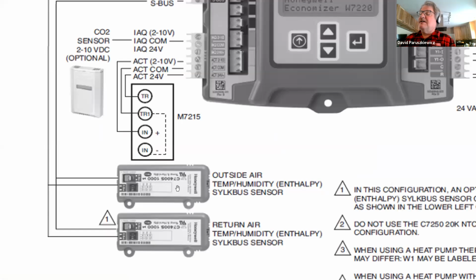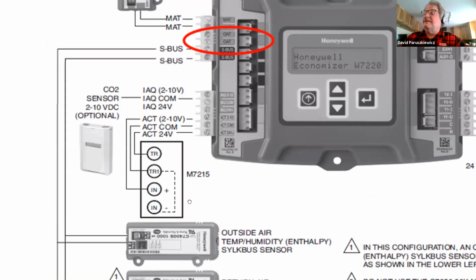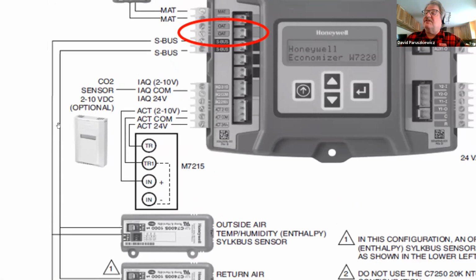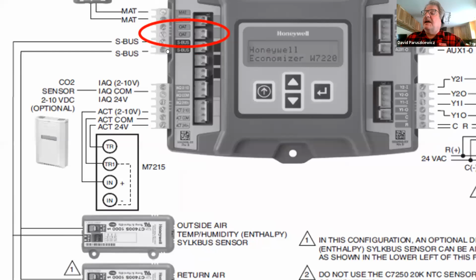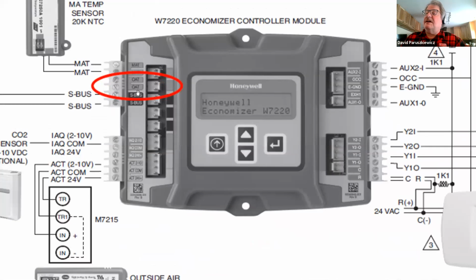Okay, these are enthalpy sensors. Enthalpy is temperature and humidity together. So if I look, the enthalpy sensors are tied into this S bus. That's Sylkbus, that's Honeywell's name for this. And up here, see the outdoor air temperature terminals? There's nothing connected. That's for dry bulb. Dry bulb is strictly temperature. If you're putting an economizer on in Michigan, we don't even bother with dry bulb, because if it's above 60 outside, you can't economize with dry bulb.